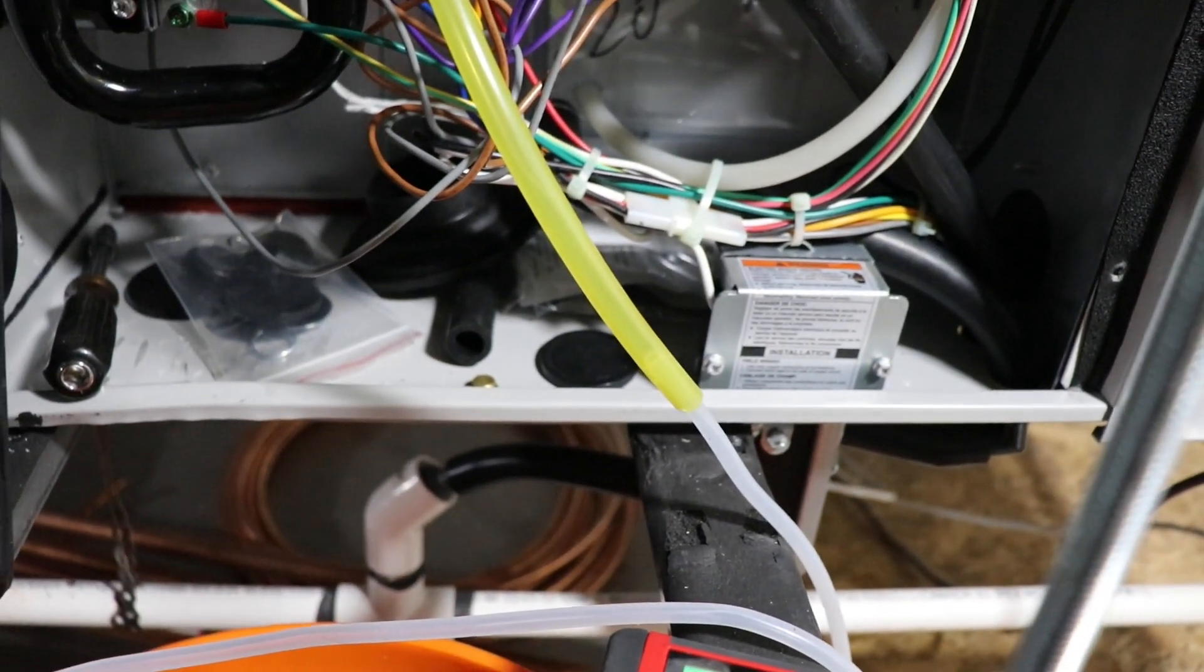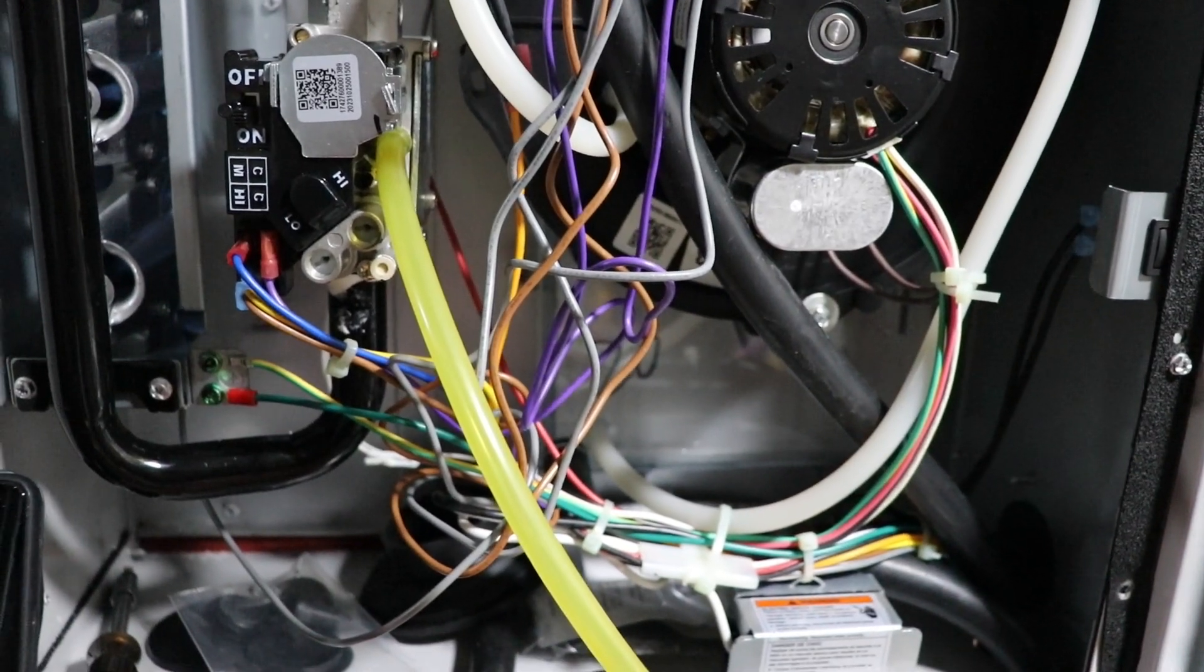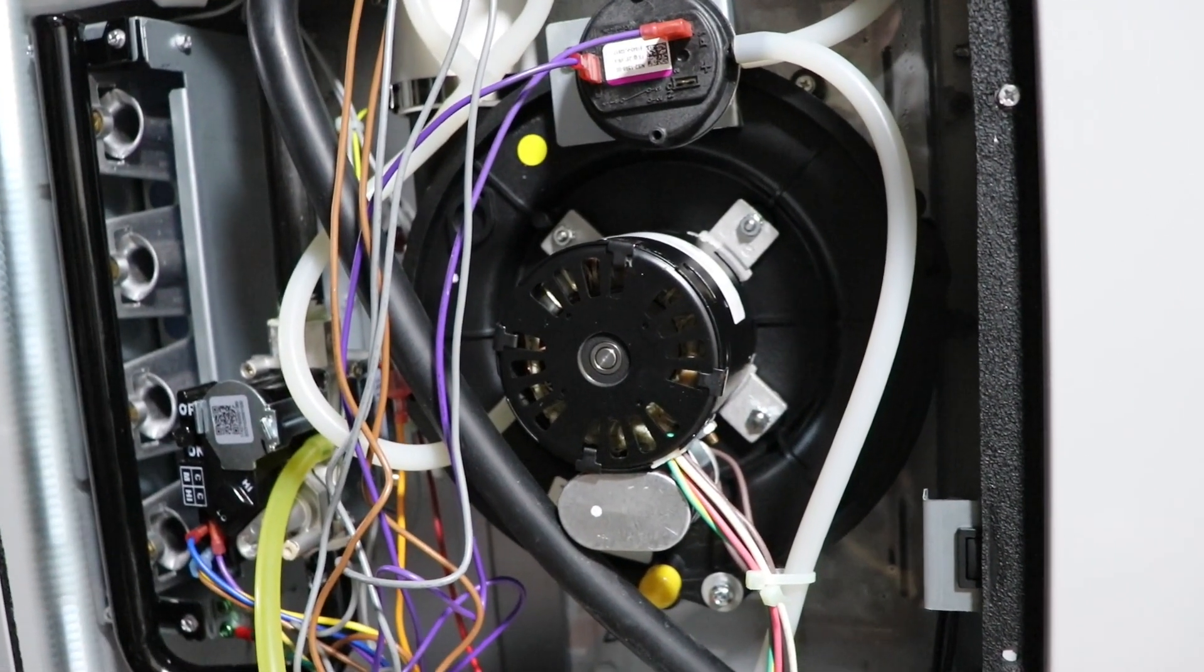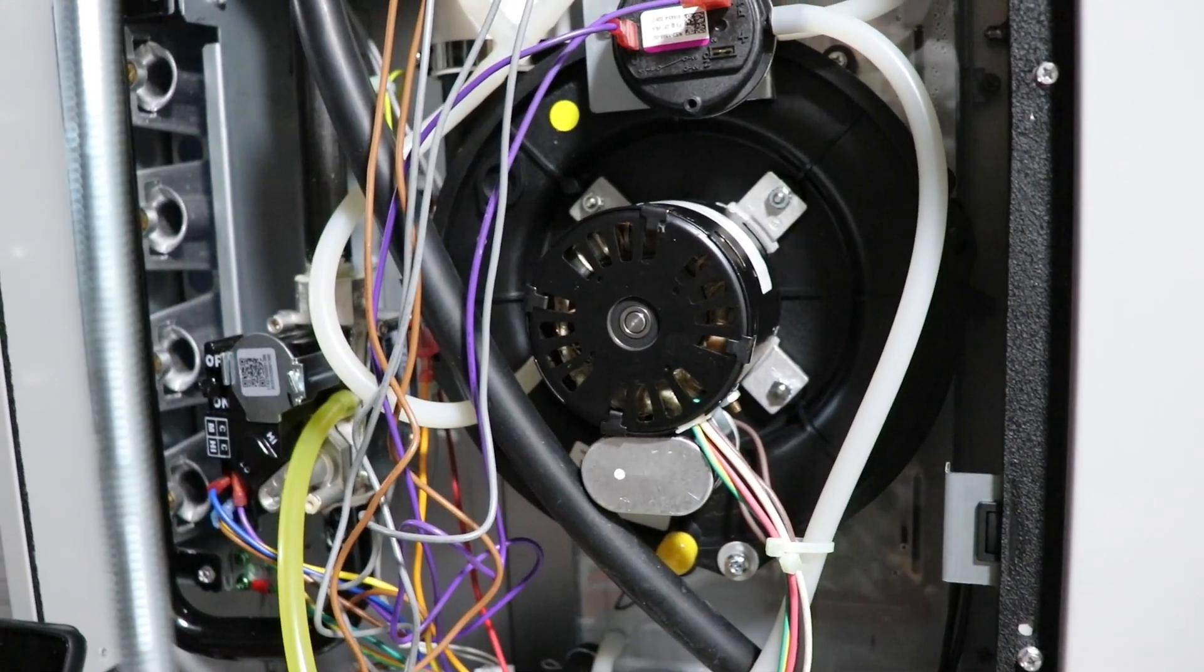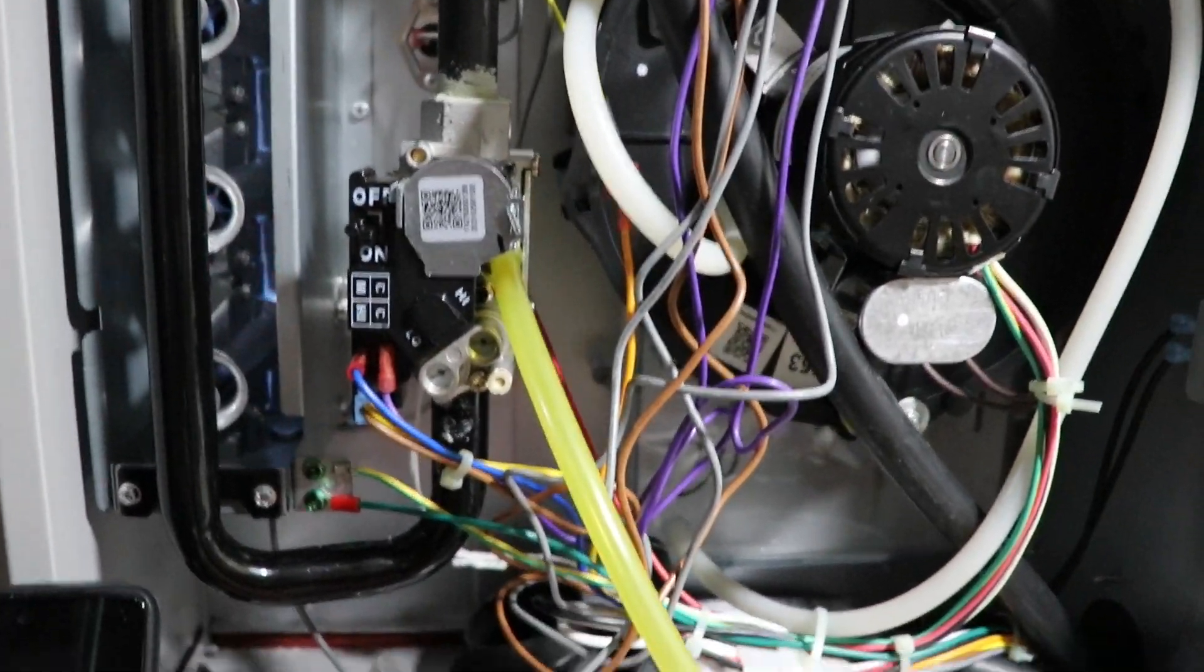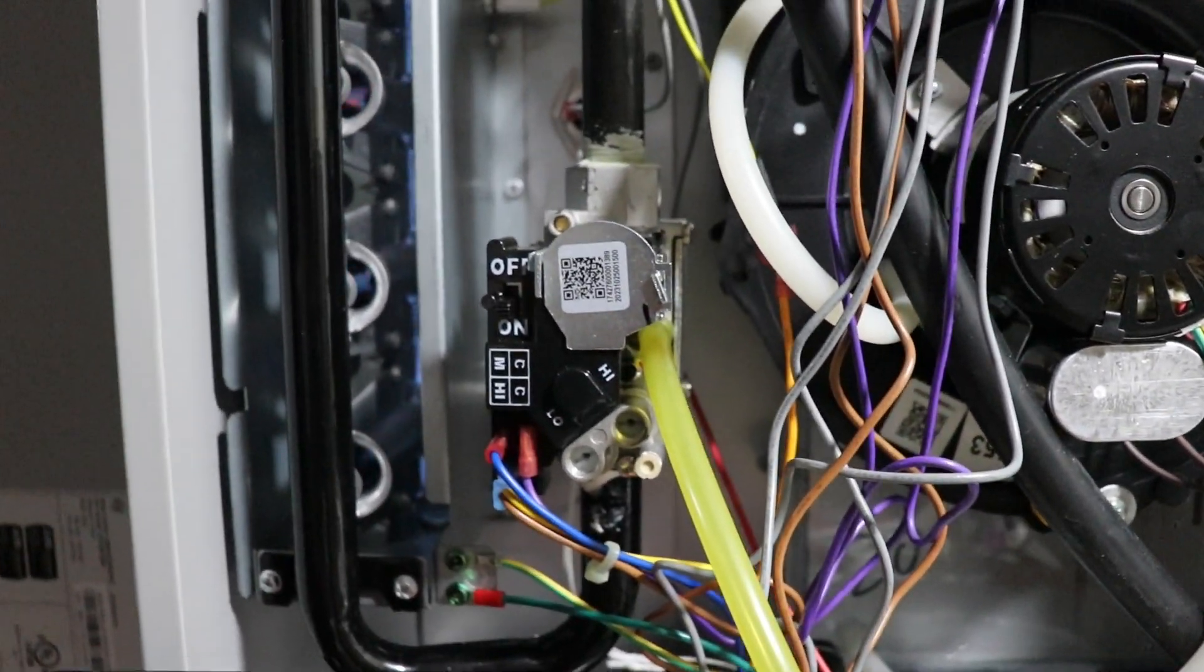Now I'm going to shut the furnace down. It seems like if you short cycle this furnace, it'll start tripping the E2 code in here. You can hear the condensate kind of in the blower fan, and it takes like three or four attempts before it fires up again. That's not ideal. Doing the testing kind of puts it in a funny situation, I think, is the case anyway.